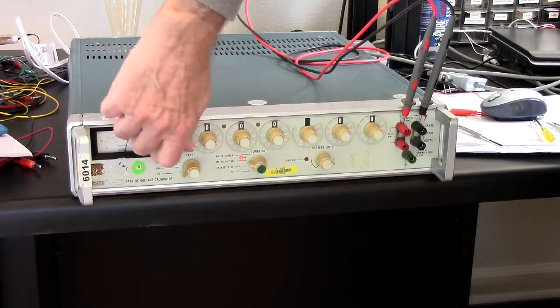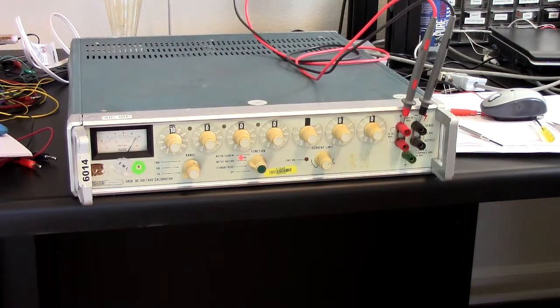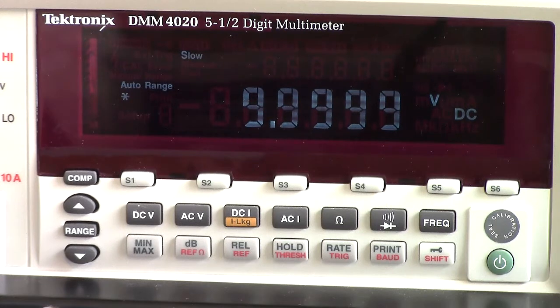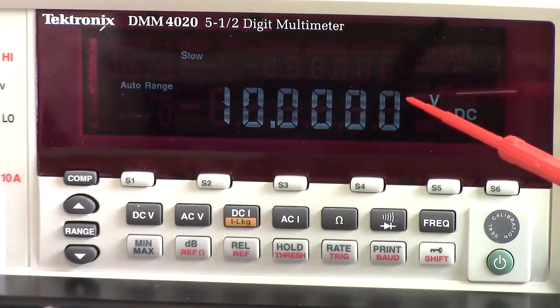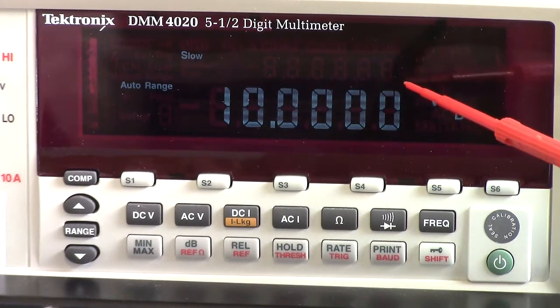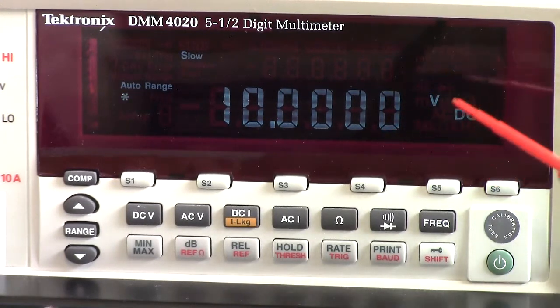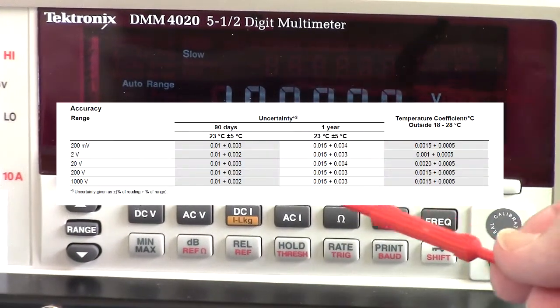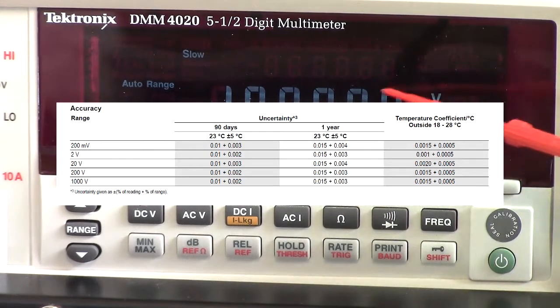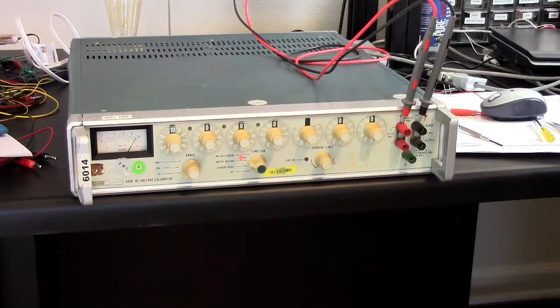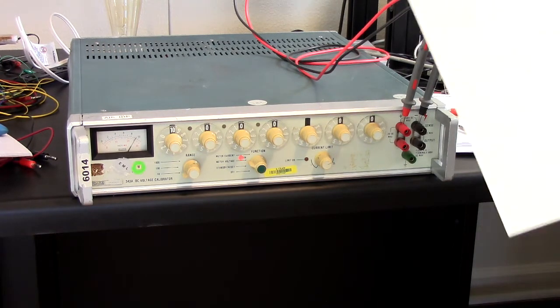Crank it up to 10 volts. What the heck? 9.9999. That's pretty good. That would be 10. That would be within spec on this anyway, because if you read the specs, this is like 0.015 percent accuracy, plus or minus a digit or two in the last digit, from the calibration, which was done a few months ago, in July. It's now December.